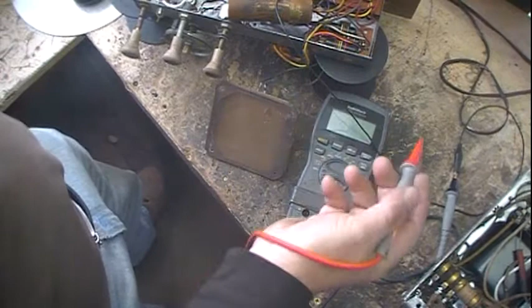So when in doubt, change the setting range when you're checking resistance and see if you can ever get a reading. If it's saying it's shorted, keep turning it down in scale until you get a reading. If you never get a reading and it is truly shorted, then it is. If it's saying it's out of limits, or it can't read it, or it's open, then start going the other way.